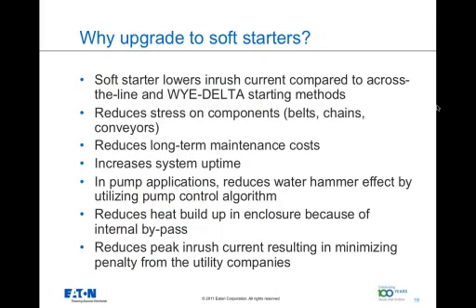And that water hammer can be significantly reduced, and in the majority of cases eliminated, by using the pump algorithm that is available in a typical soft starter. By usage of the bypass contactor, the heat buildup in the enclosure is also dramatically reduced by using an integrated bypass soft starter. Finally, the reduction in the peak inrush current reduces the penalty that is levied by the utility companies.